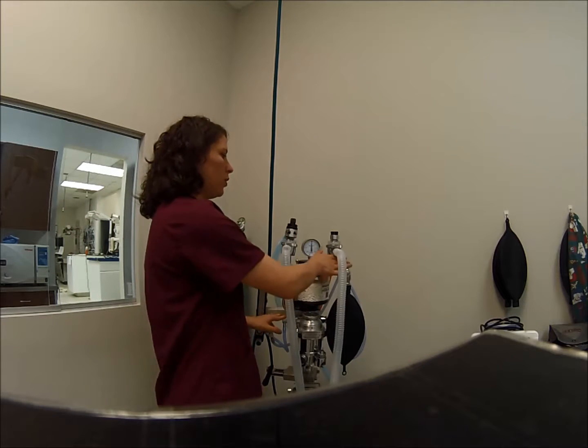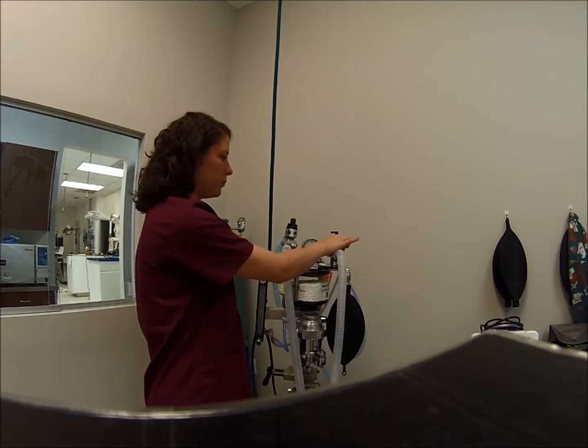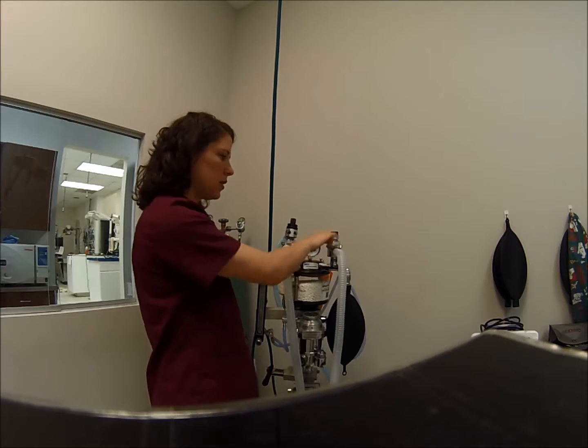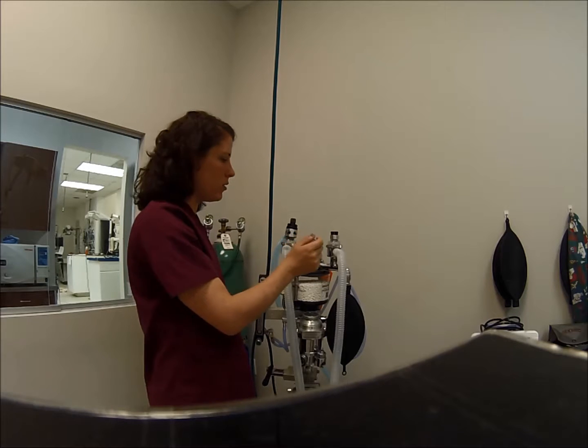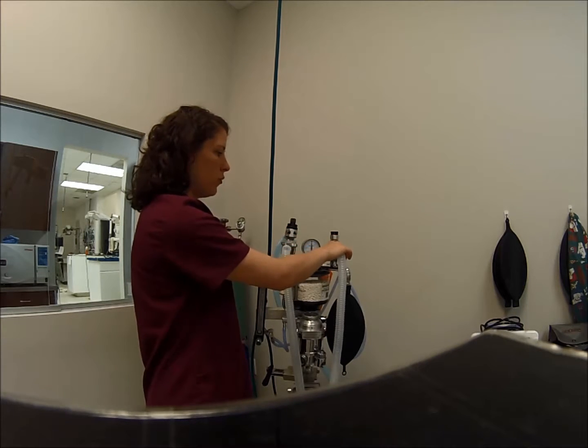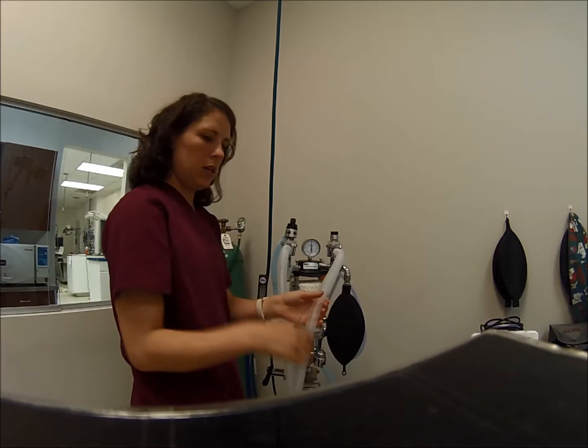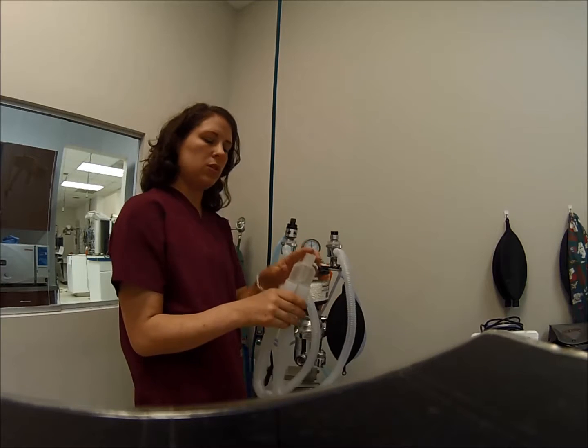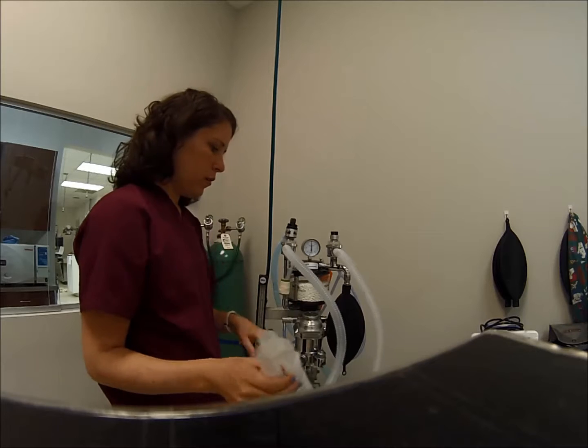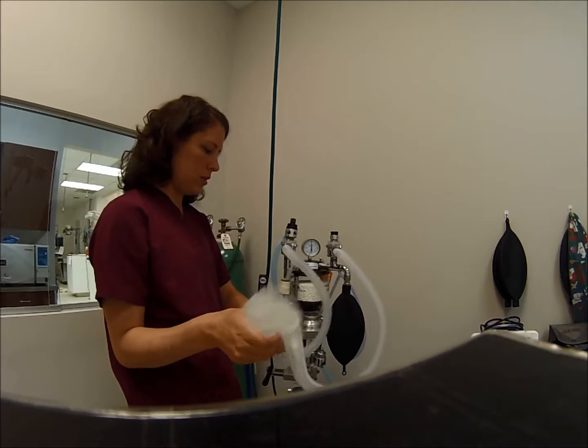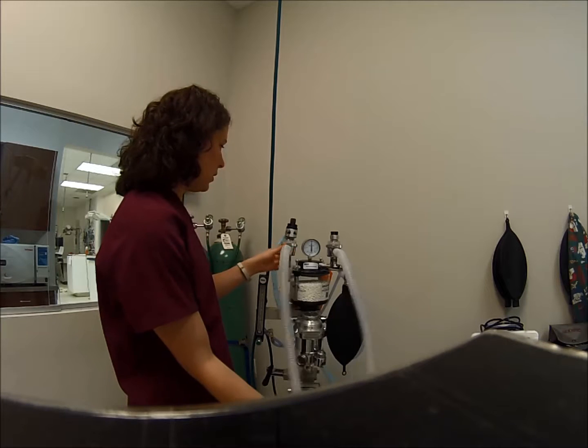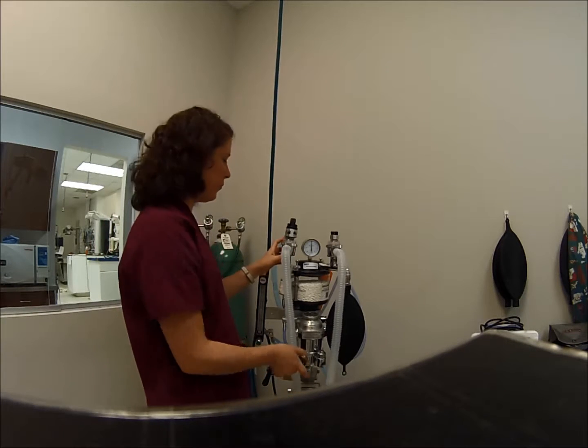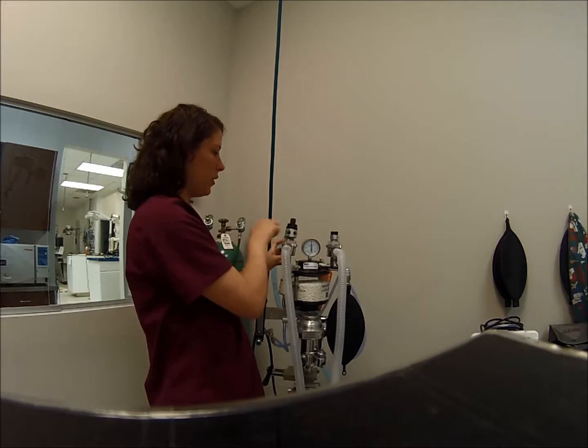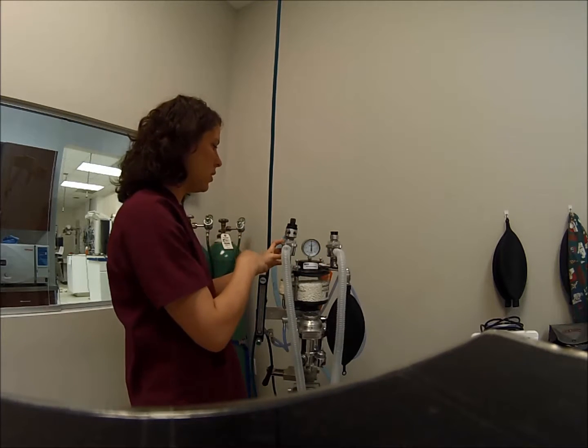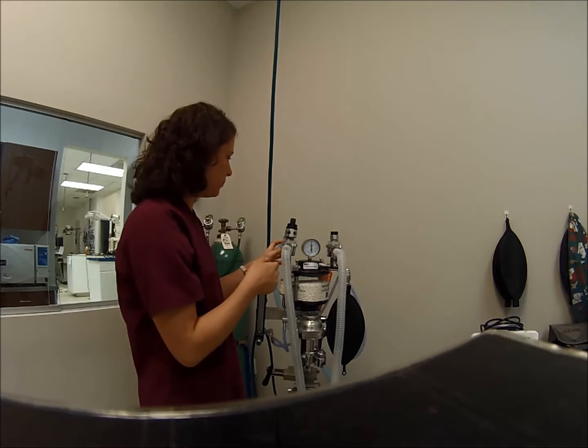Next you have your unidirectional inspiratory valve up here, which houses a disc that will flutter whenever the patient inspires, and the gases will travel through the valve down this side of the corrugated Y-piece tubing and into the patient. This end is hooked up to the endotracheal tube. When the patient expires, it will travel up this side of the Y-piece and into my unidirectional expiratory valve, which works similarly to the inspiratory valve in that it flutters also when the patient exhales. It's a good indicator of the patient breathing.